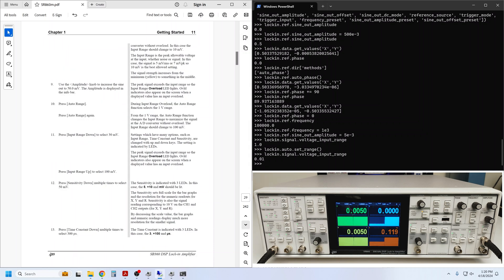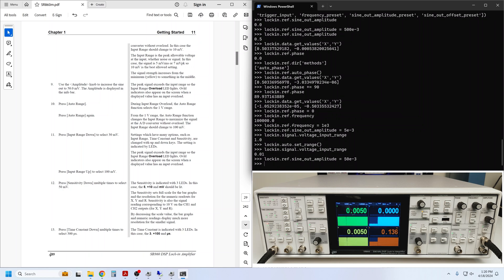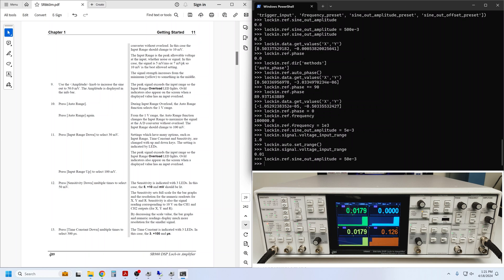Now we are supposed to adjust the output amplitude to 50 millivolts, which is larger than the new input range, of course, so that we intentionally cause an input overload. We can see clearly from the front panel that there is an input range overload. How do we get this information remotely? There are a couple of ways.